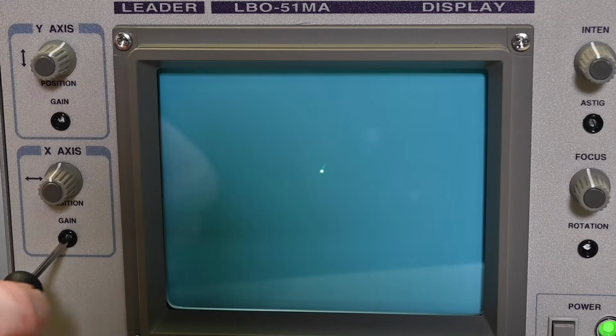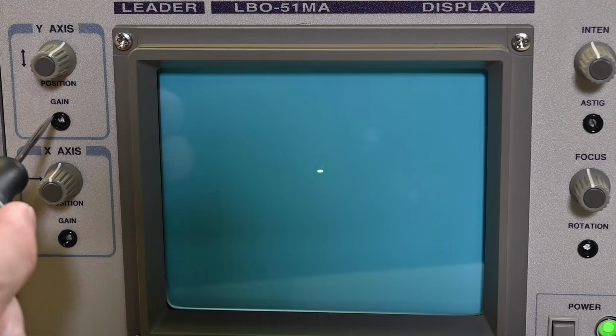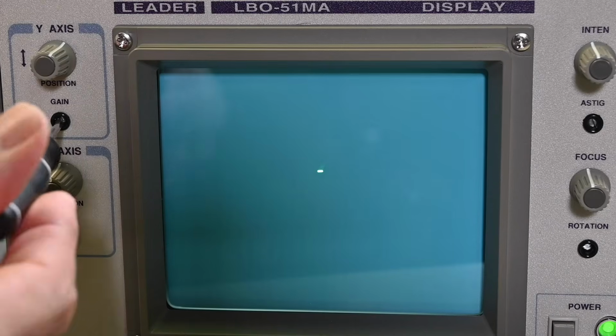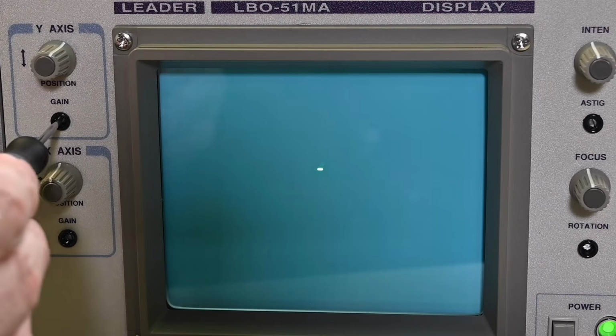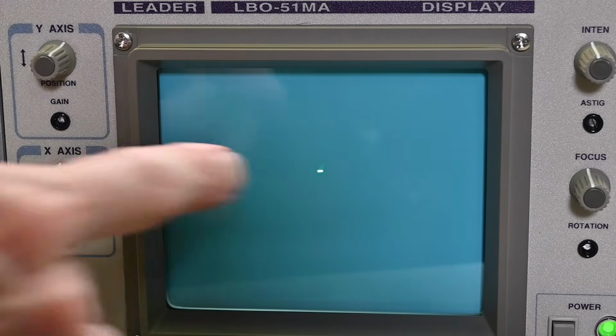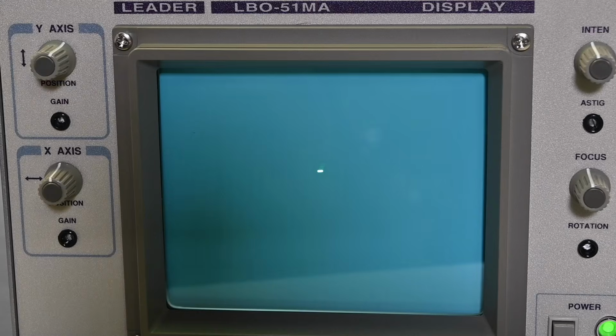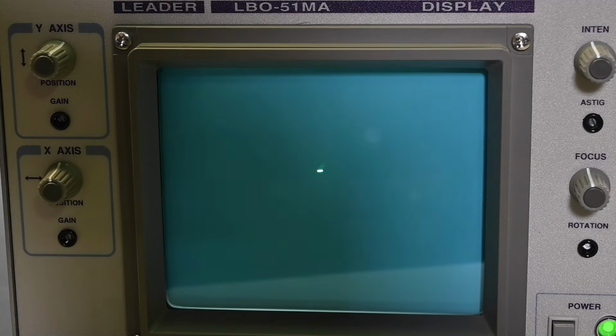But of course it should work with the gain turned all the way up, like that. Now the gain on the y-axis is also at its maximum, and if I turn it down, it doesn't change anything. There's no signal, so we're not really seeing any change at all, and it doesn't change the deflection on the y-axis. So I thought, well, why is it picking up this noise or interference that's causing some deflection on the x-axis? So I started looking around inside the instrument.